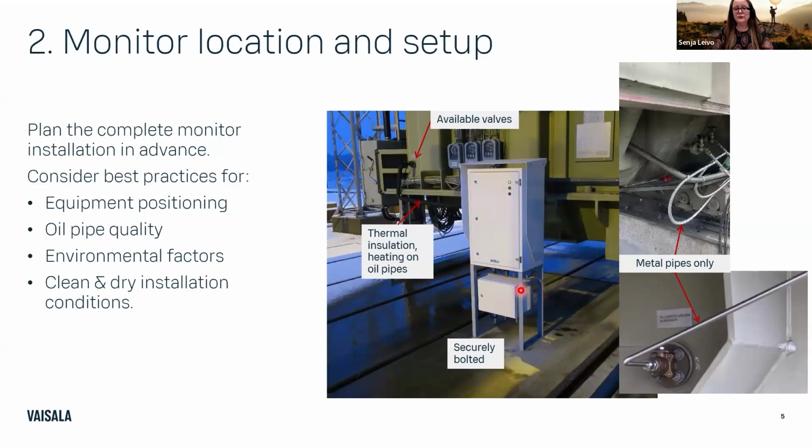I have taken a few things here as the factors. Like, for example, what are the climate conditions? If you can see from the photo, we have snow here, so it's Finland. Arctic conditions. So this specific site, they had during wintertime something like, sorry guys, now I'm in Celsius scale, so -32, I guess, was the lowest temperature. Bottom oil temperature in this transmission transformer was -15 degrees C.